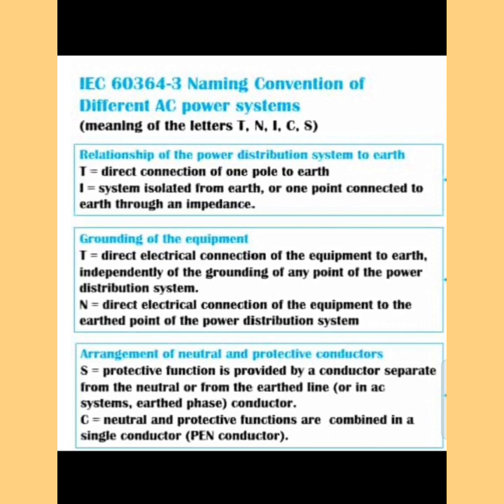The second letter describes the grounding of the equipment. Again it has two options: T means direct electrical connection of the equipment to earth independently of the grounding of any point of the power distribution system; and N means direct electrical connection of the equipment to the earth point of the power distribution system.